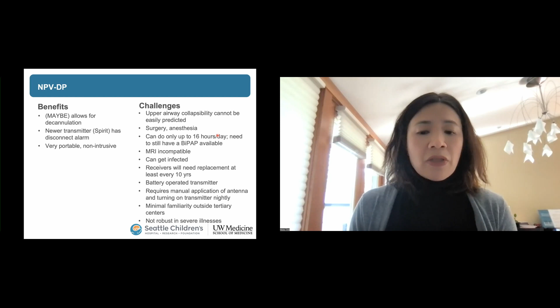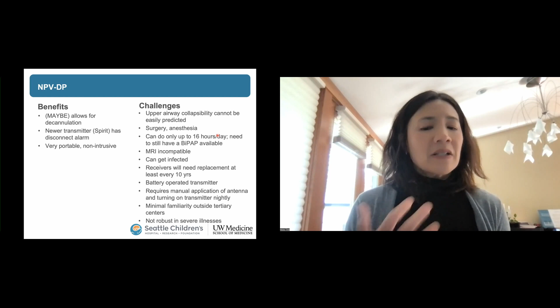They are not MRI compatible. So that is a major ding as we move toward using MRIs for various diagnostic imaging. Any piece of these can get infected. The receivers will need replacement at least every 10 years. The transmitter itself is battery operated, which means that it's dependent on a human to change those batteries every so often. It requires manual application of the antenna and turning on the transmitter nightly. So this is not an automatic system either. There's minimal familiarity with diaphragmatic pacing outside tertiary centers, and it tends not to be as robust during severe illnesses.